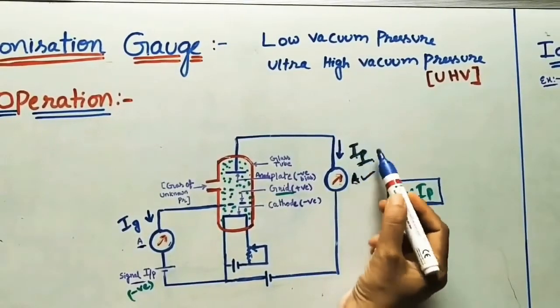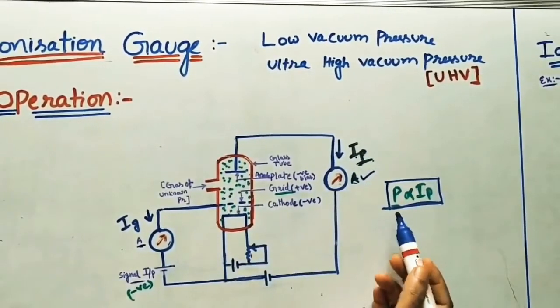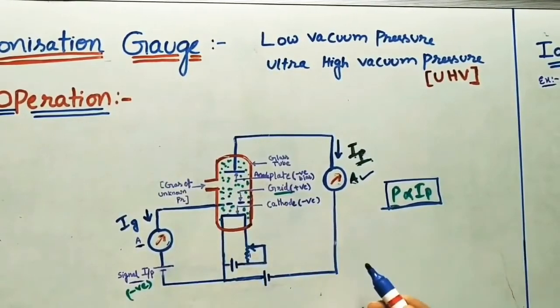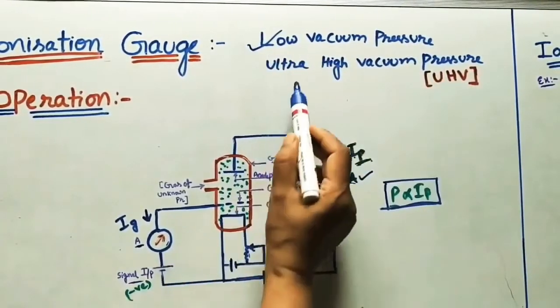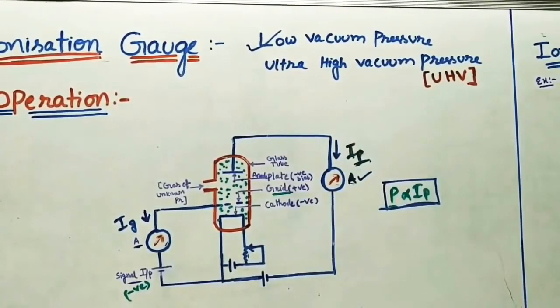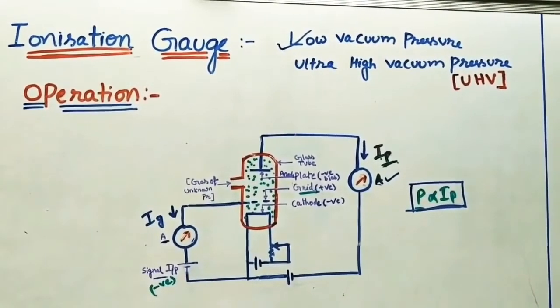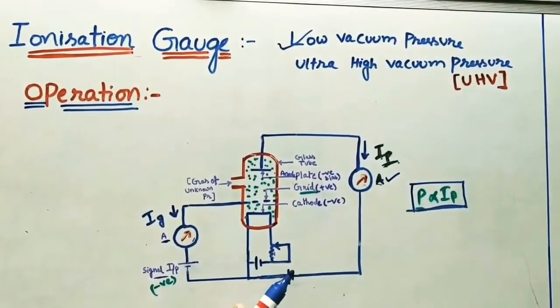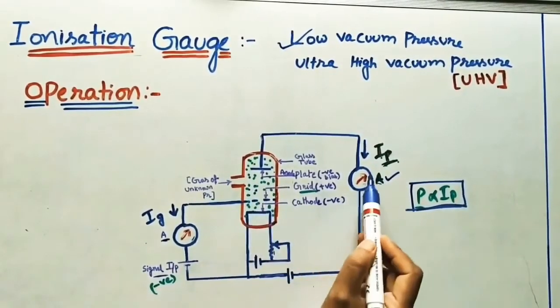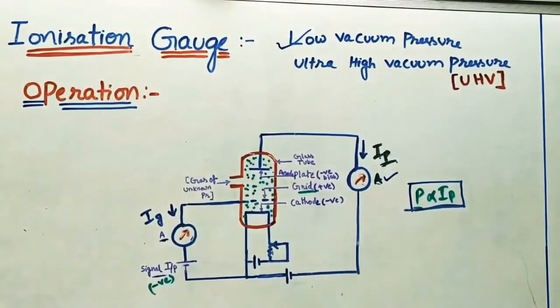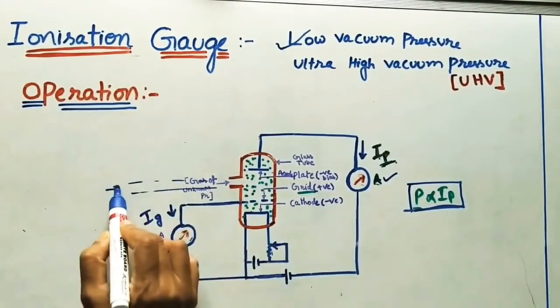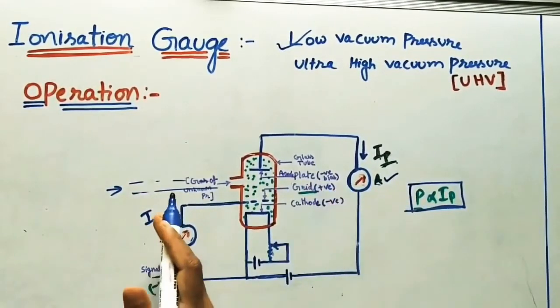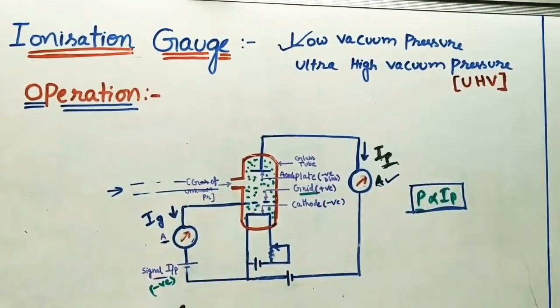Finally, the ion current IP will decide the pressure P value. For each and every gas, there is a separate calibrated scale. This is the main operation of the ionization gauge. The applications are: they are used to measure low vacuum pressure and ultra high vacuum pressure effectively. The advantages are it is very sensitive and gives very accurate values. The response is fast — whenever gas enters, it immediately gives a current value from which we can find P. Also, measurement can be done from a long distance; the gas can be supplied remotely while the ammeter and circuit are kept in a different room.